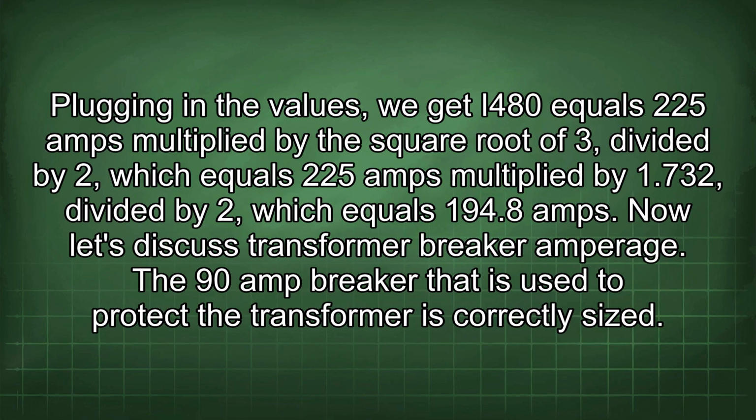Plugging in the values, we get I480 equals 225 amps multiplied by the square root of 3 divided by 2, which equals 225 amps multiplied by 1.732 divided by 2, which equals 194.8 amps.